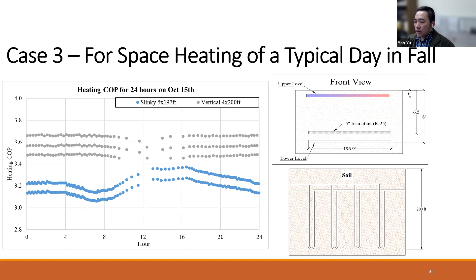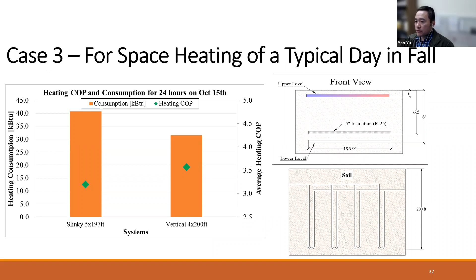loop. So this slide shows the corresponding heating energy usage of the heat pump along with the daily average heating COPs. The vertical boreholes have lower energy use due to their higher efficiency, but the result also shows that we can still meet the space heating demands in fall for this house by using the upper loop closer to the ground surface. Again, the idea of using the upper loop for space heating in this season is to minimize the use of the ground where the lower loop is buried, to make sure that the lower loop is ready for the coming winter in order to maximize the system efficiency for space heating.